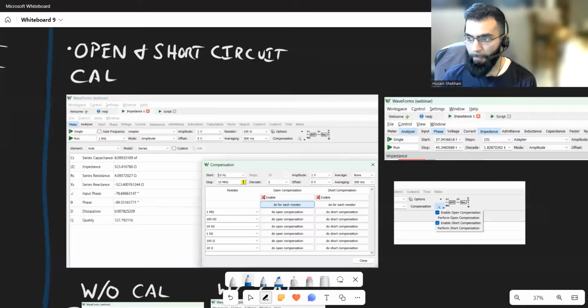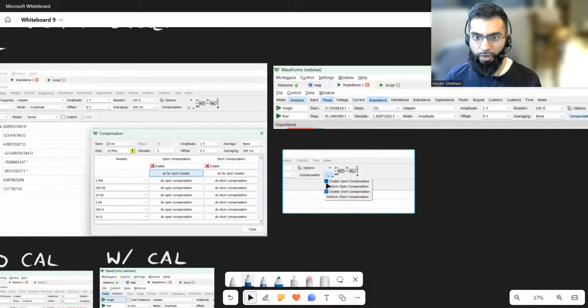So by going into the program, and I'll just do it in the program, it's a little bit more friendly there. You could go into this button here, compensation, and you can compensate for each resistor value, or you can compensate for just the settings you already have loaded using this function here, perform open circuit or short circuit compensation. Note that you have certain settings that you compensate for, like your amplitude, if you're doing averaging of measurements, and the minimum length of time of a measurement too. So note that you have to set those settings in order to do the compensation, or it's not as valid as it could be. And you also make sure you enable it by checking the check mark here in the little toolbar menu.